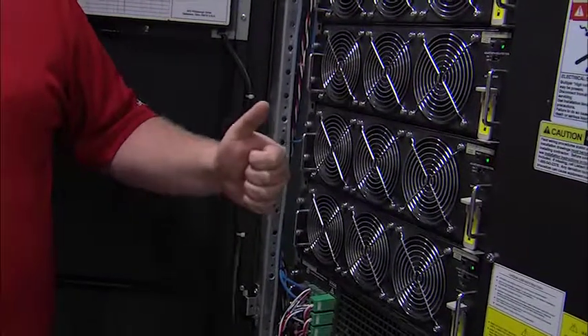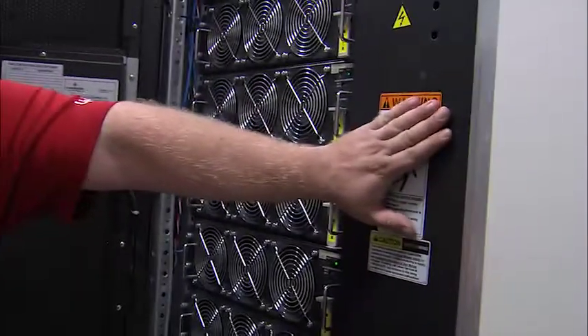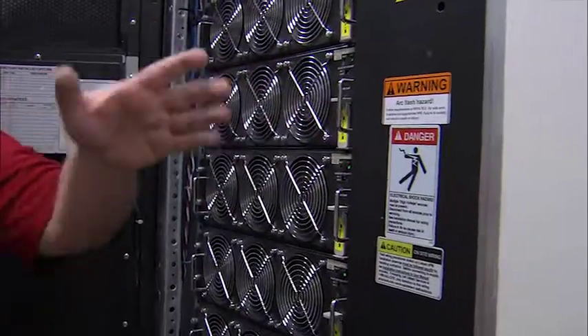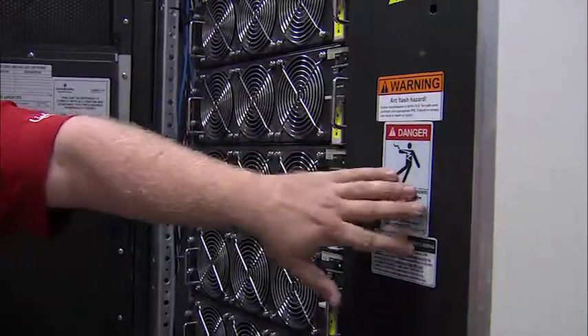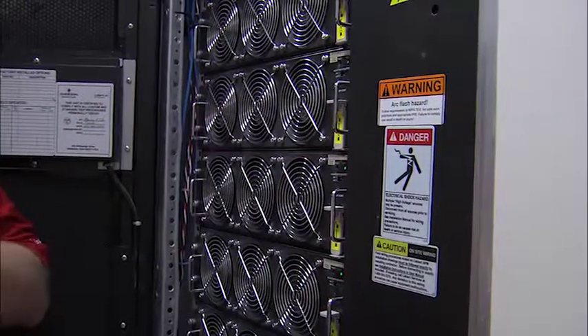So as you can see, there's only very few components to this system. You have your inverter rectifier module and your static bypass module. If any one of those had to be replaced, that's something they grab off the van and put back in, and you're back up and running. If you break a breaker, you have to really kick those and do something bad to break them. And underneath this panel here are all your input and output connections. So there's no mechanical device within here. The only mechanical or working devices are here.